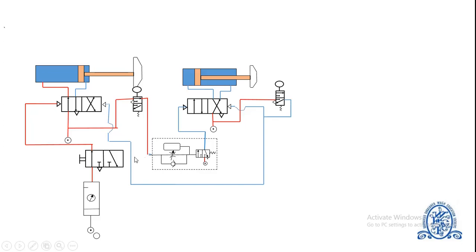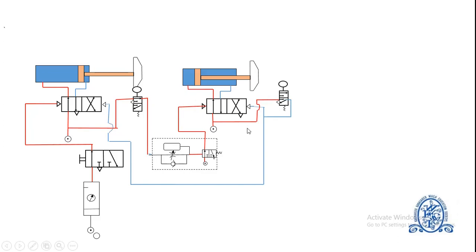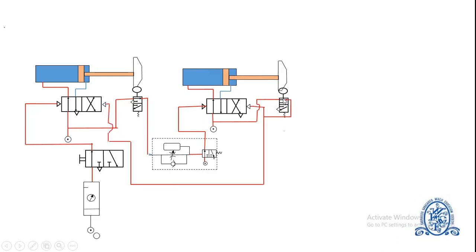However, the 3x2 direction control valve in the time delay valve will actuate after 10 seconds and then will operate the direction control valve 2. The piston of cylinder 2 then will go to extension. After full extension of cylinder 2, the roller operated valve ROV2 will go to on position, providing impulse signal to operate both DCV1 as well as DCV2.